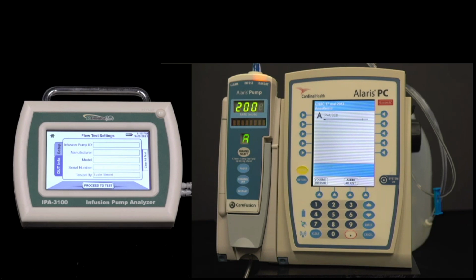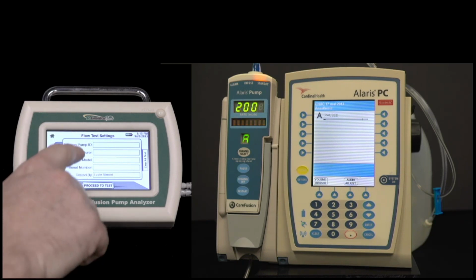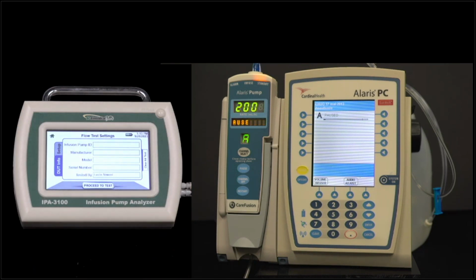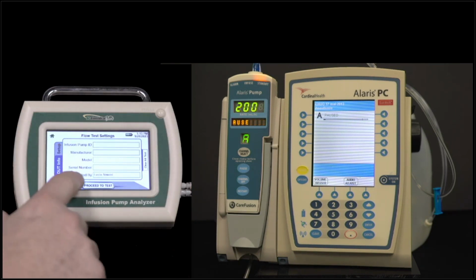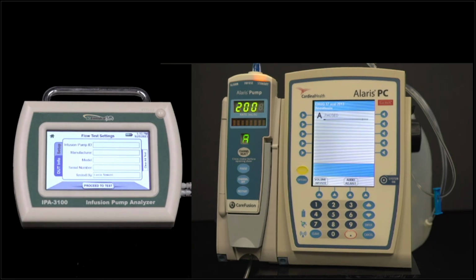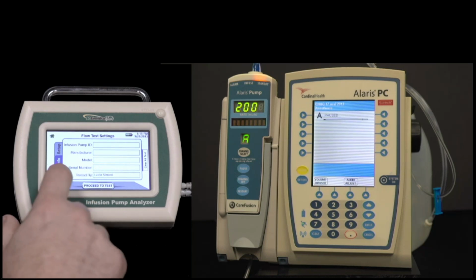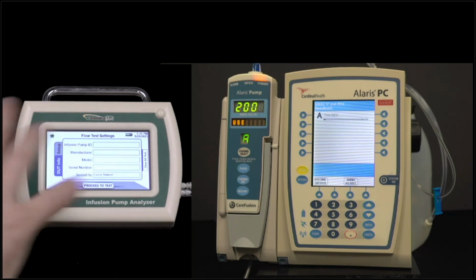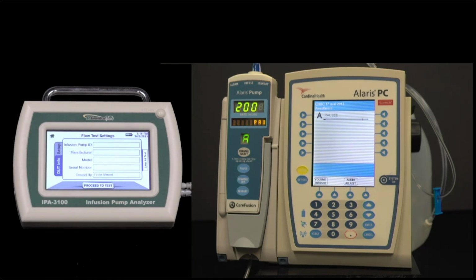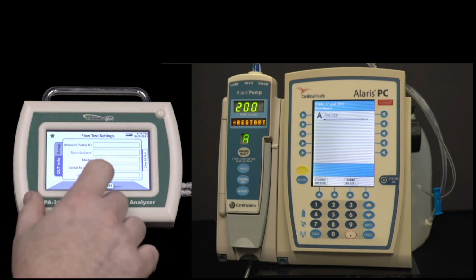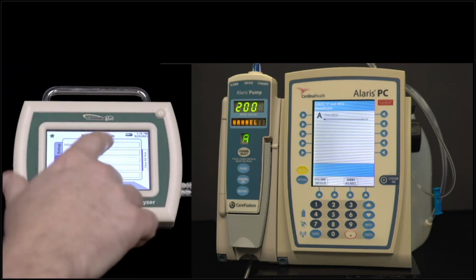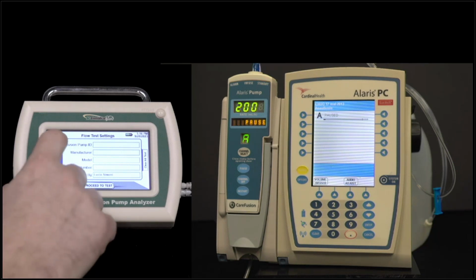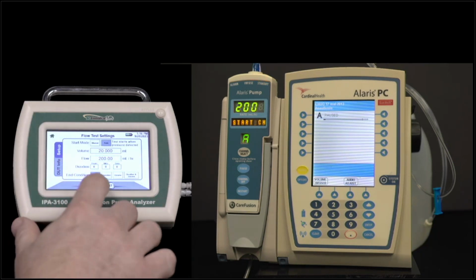We also have the option to put in information about the device under test. This will store, I can put in if I have an identification number for my pump, a tag number, the manufacturer model, all of that can be entered here, as well as who's doing the testing. So then I can enter information about my DUT. That's stored. We have onboard storage on the unit. It can store these test records, and that will be included in that record. But again, I can leave that blank if all I want to get is measurements.